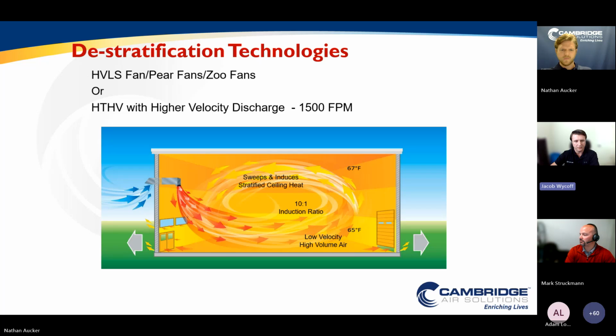Another benefit of 100% outside air units is that you are positively pressurizing the building, which is going to reduce that infiltration you're seeing down near the floor through those open dock doors. When applied correctly, HTHV is going to see anywhere from a 2 to 3 degree temperature difference from the floor up to the ceiling and across the walls. So that's how we avoid stratification in these spaces.